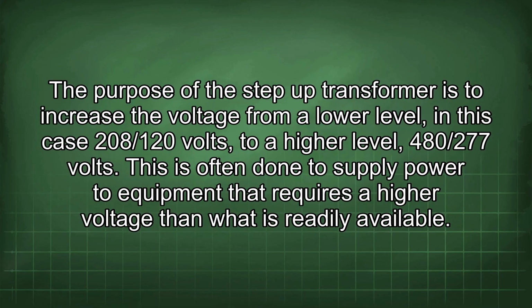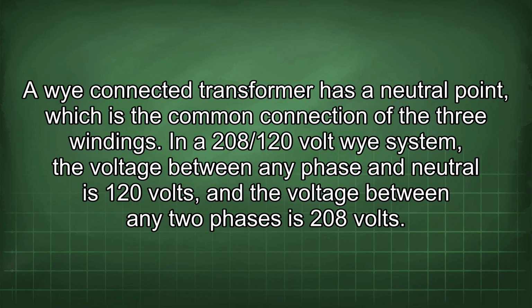The purpose of the step-up transformer is to increase the voltage from a lower level, in this case 208/120 volts, to a higher level, 480/277 volts. This is often done to supply power to equipment that requires a higher voltage than what is readily available. A Y-connected transformer has a neutral point, which is the common connection of the three windings. In a 208/120 volt Y system, the voltage between any phase and neutral is 120 volts, and the voltage between any two phases is 208 volts.